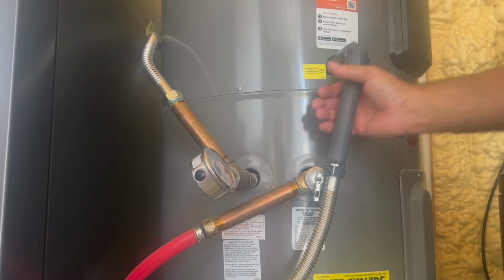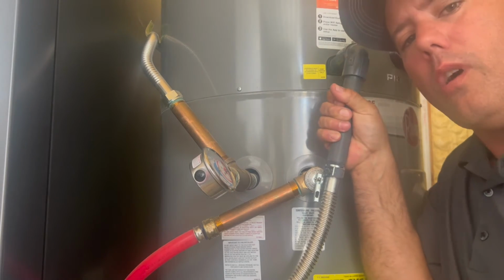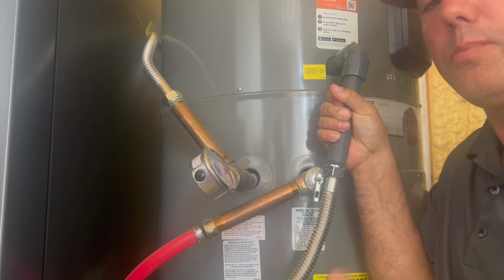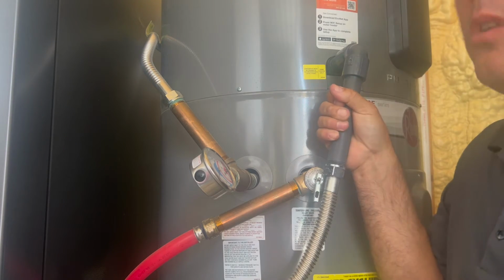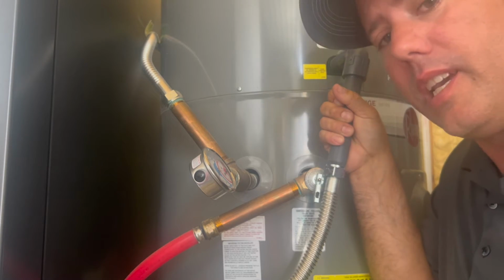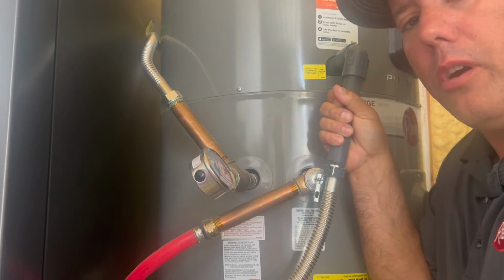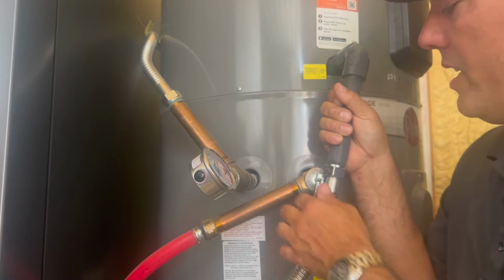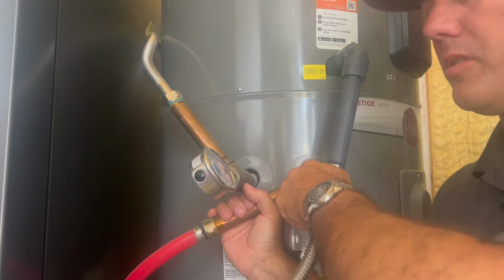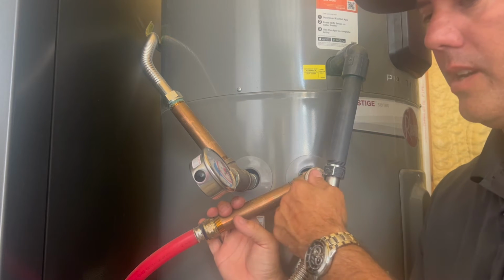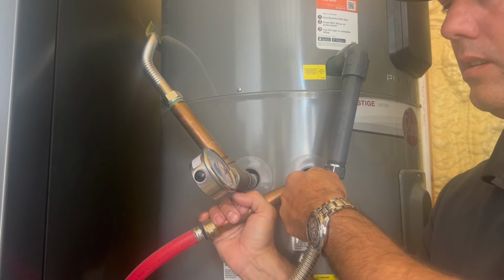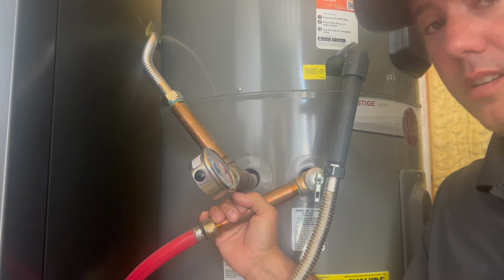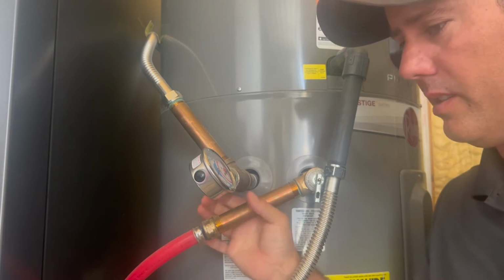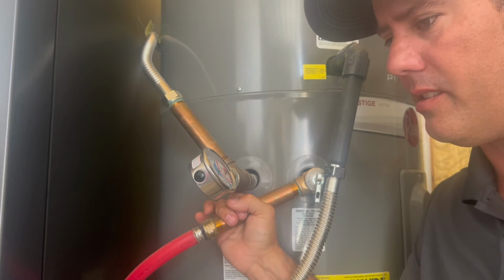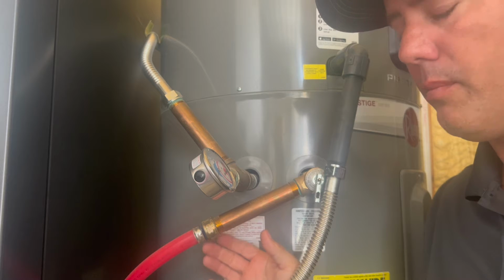Okay, let's talk about some troubleshooting steps. If we're dealing with a situation with not enough hot water or water not hot enough, we might want to look at the display and see what the temperature is set at. This one says 120 and it's not calling for heat, which leads me to believe the water heater would have 120 degree water in it, or at least it thinks it does. So, an easy way to verify that, and this is of course just going to be a touch verification, we're going to run some water through the T&P. That's really hot. It's almost too hot to touch for a few seconds. That's going to be pretty close to 120.